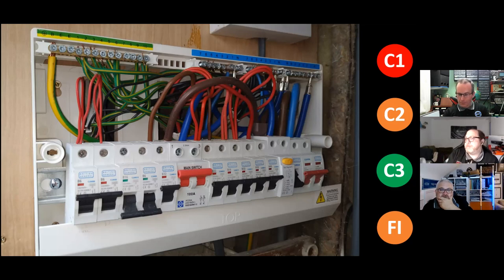I really don't like those types of lugs. It worries me when I see boards with all that metal on show, and it looks like it's putting strain, that neutral in the top right corner looks like it's putting massive strain on the neutral bar. We've seen a lot of neutral fires, and it's often that lugging that's one of the culprits. Okay, so I'm assuming here then we're going to have circuits that need an RCD but now don't have one. That's right. Okay. Different manufacturer assembly.